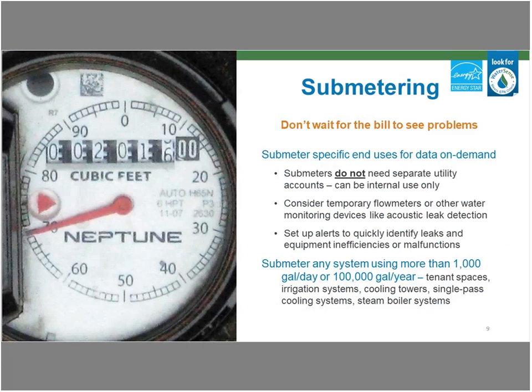One thing I want to clarify is that adding submeters does not necessarily need a separate utility account. They are mostly used for facilities to manage their water use internally instead of waiting for a monthly bill or even a quarterly bill. This can cut response time for leaks or malfunctions significantly and save money. There are some flow monitoring devices that can be connected to the building automation system or otherwise connected to the web that can send alerts to let you know that a leak is detected.